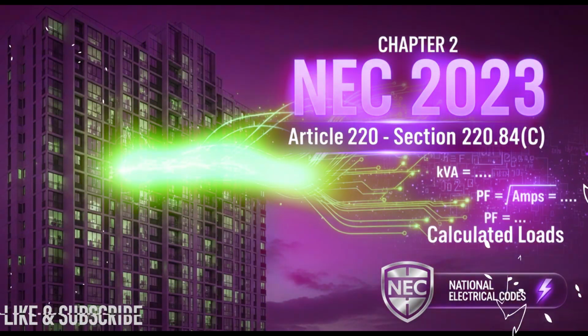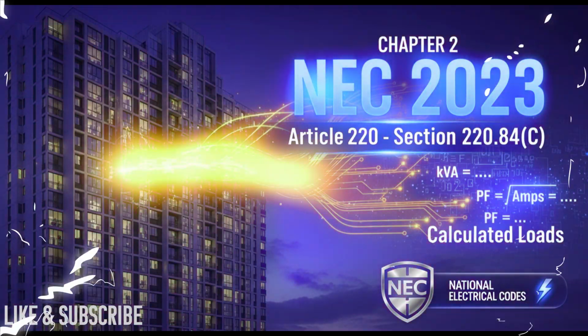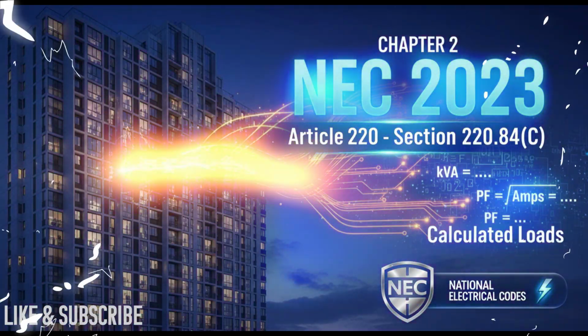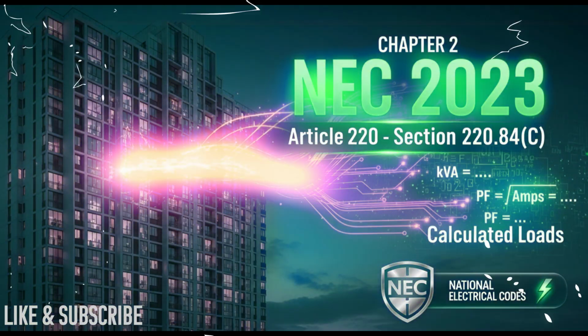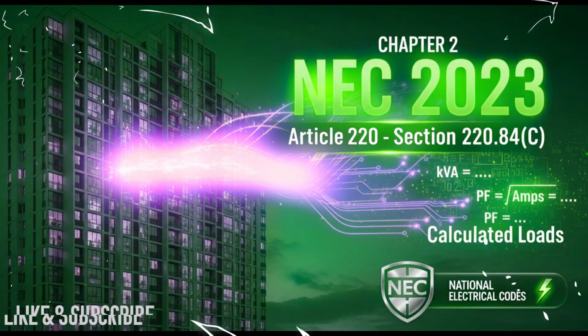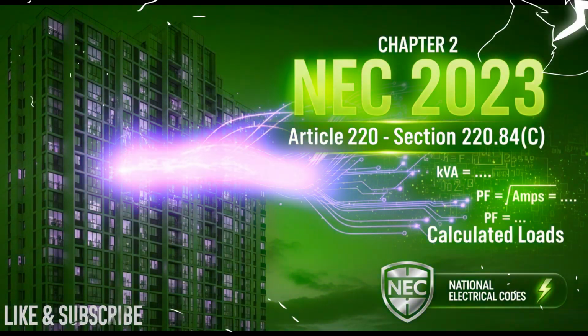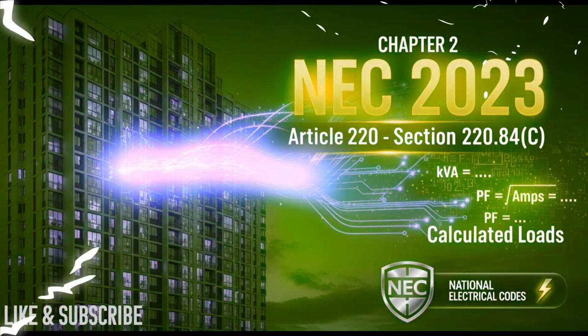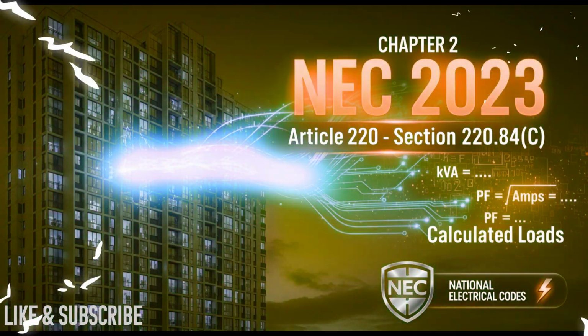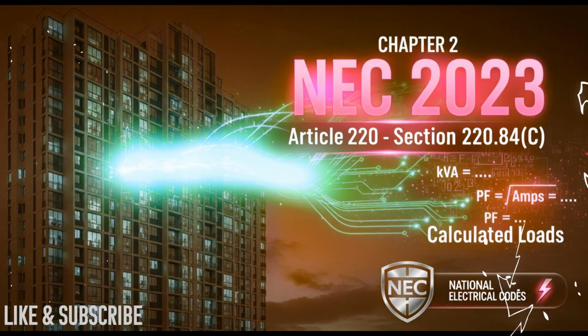Where do we start? Okay, input 1, general lighting and receptacles. This is the base layer, you could say. What are the exact numbers the code demands here? Right, the code is super specific. It says designers must include 33 volt amperes per square meter, or, because we often work in feet here, 3 volt amperes per square foot. That's for the general lighting and the general use receptacles, the standard wall outlets.